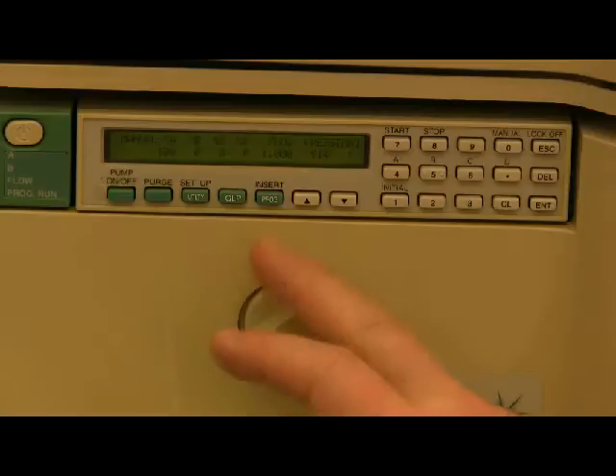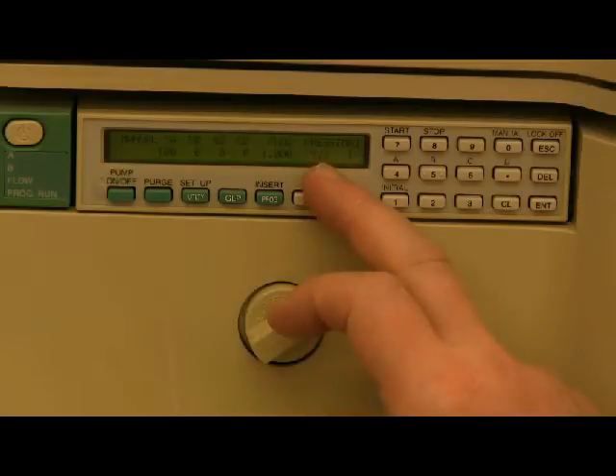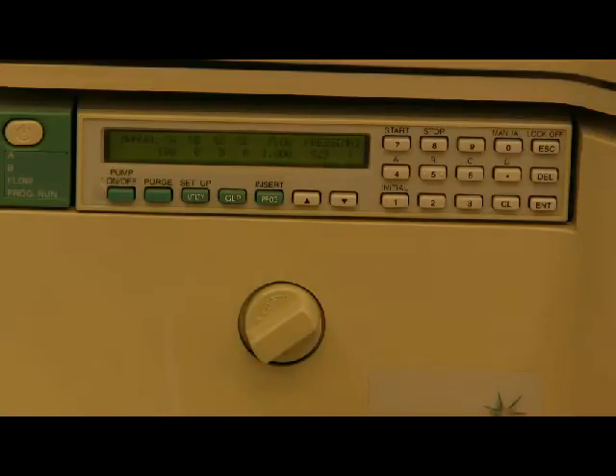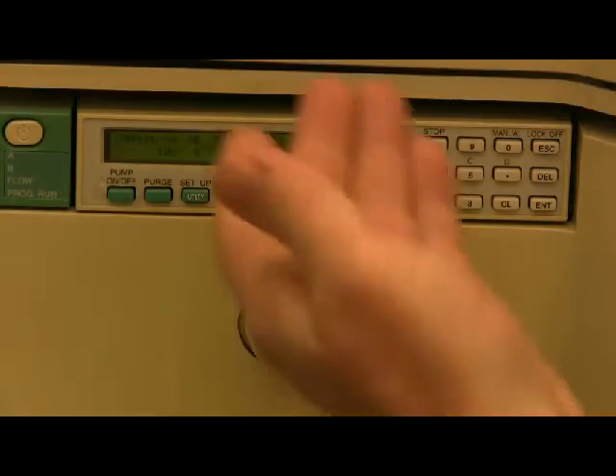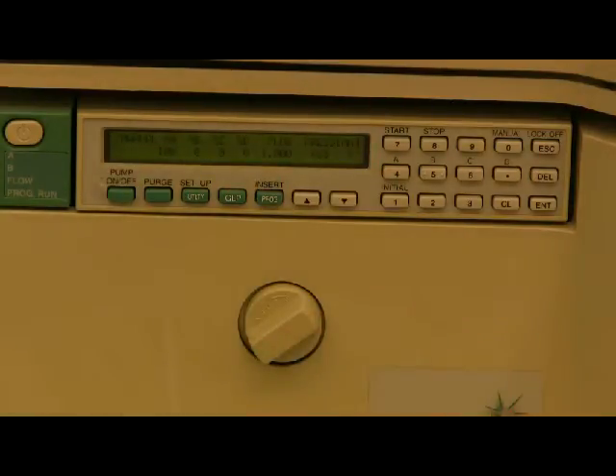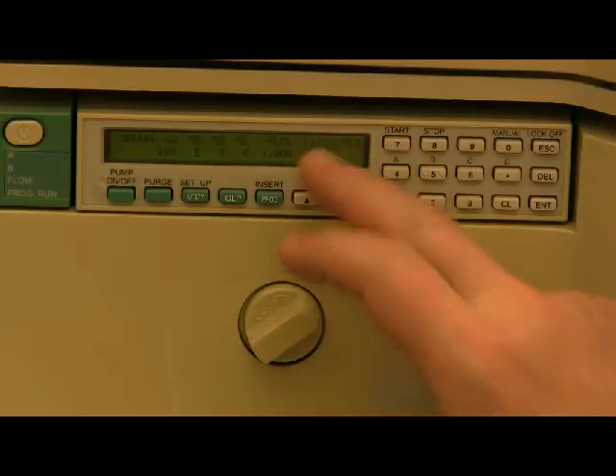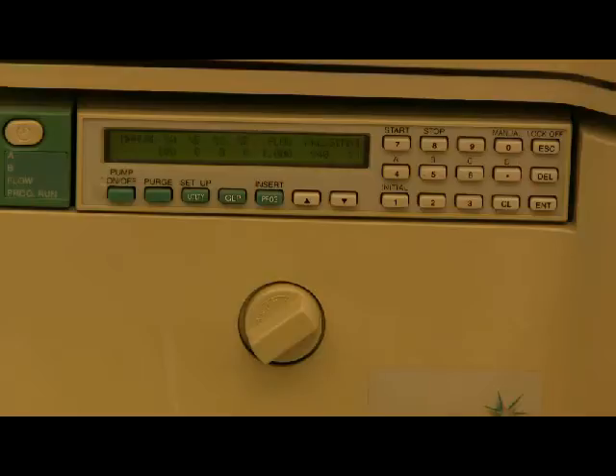One thing with this instrument, if it's been sitting a while, sometimes you'll get pressure fluctuation. I found the way to fix this is just by cracking this open, letting the pressure drop, turning it back on, letting it build up. If you do that one or two times, usually the pressure will build up and stabilize. If you do that and you can't get the pressure to stabilize, seek some assistance from someone who can help you.